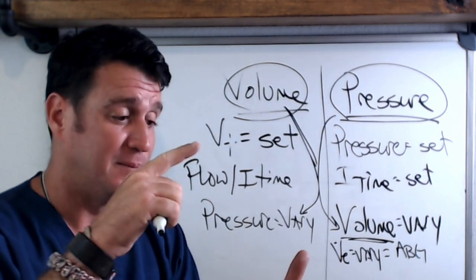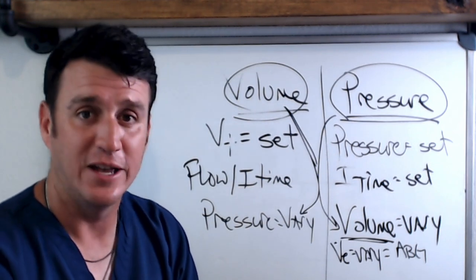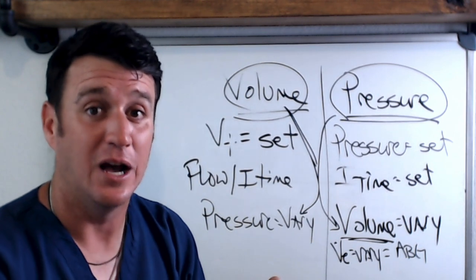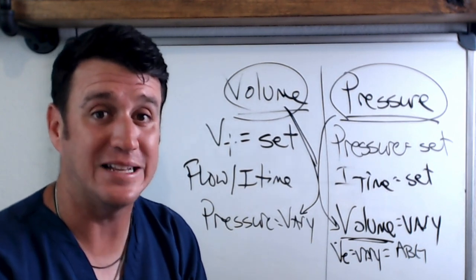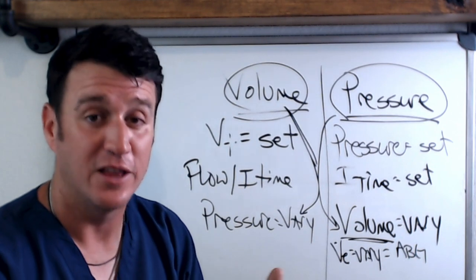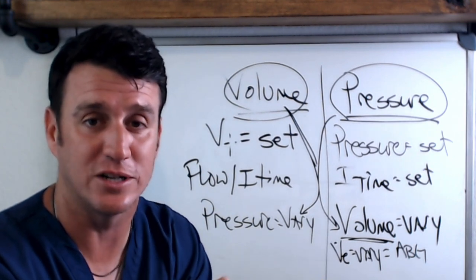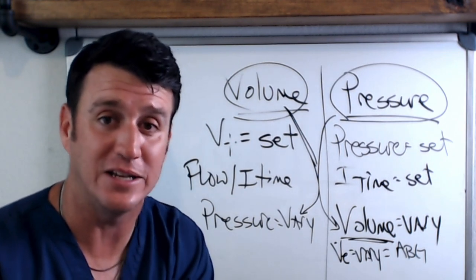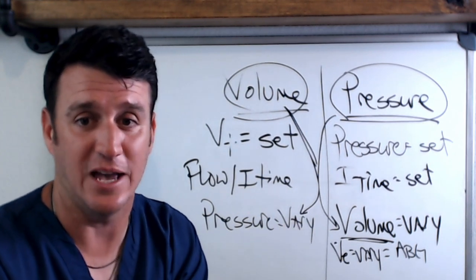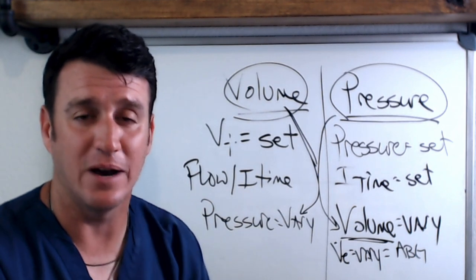Let me recap: cycle is the variable that ends inspiration. Trigger is the variable that begins inspiration — it can be time-triggered on the vent side, or patient-triggered via pressure, flow, or volume. Limits are things that will not be exceeded during the inspiratory phase. In volume control, tidal volume is set and pressure will vary. In pressure control, pressure is set and volume will vary, which means your ABGs might also vary.